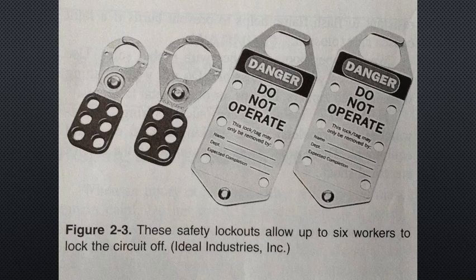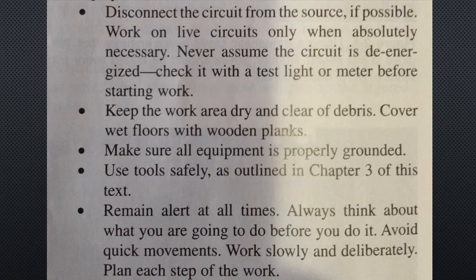Certain safety rules should be followed during the installation and maintenance of electrical equipment. Disconnect the circuit from the source if possible; work on live circuits only when absolutely necessary. Never assume the circuit is de-energized — check it with a test light or meter before starting work. Keep the work area dry and clean up debris; cover wet floors with wooden planks. Make sure all equipment is properly grounded. Use tools safely. Remain alert at all times — think about what you're going to do before you do it, work slowly and deliberately, and plan each step.